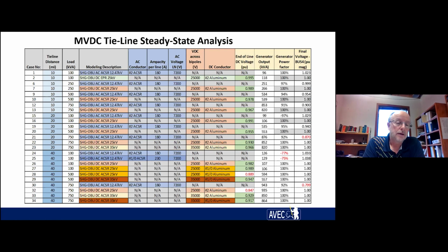We looked at AC and DC options for Kobuk, and also for future installations with longer distances between communities to intertie them potentially with medium voltage DC. You can see on the left the miles between villages, and the various loads from 100 kVA up to 750 kVA, and the conductor size that was modeled. In this case we used either number 2 ACSR or 1-aught ACSR.